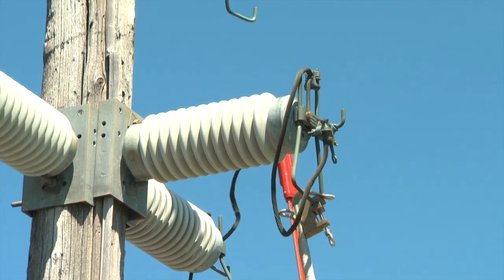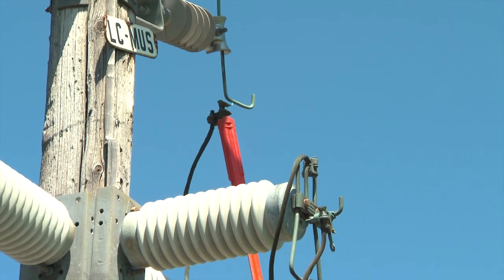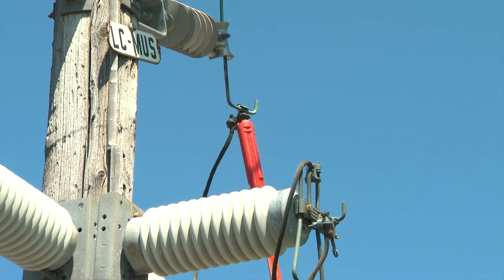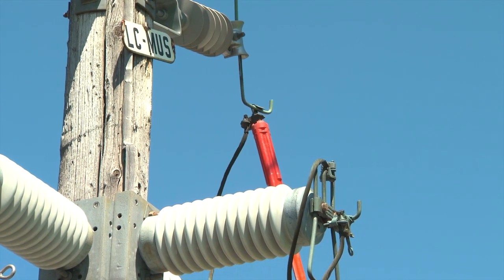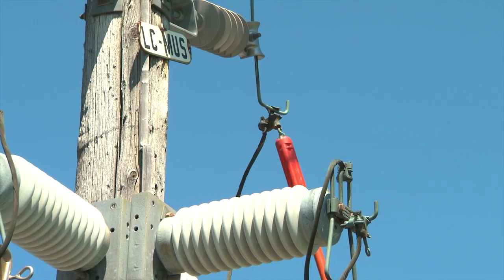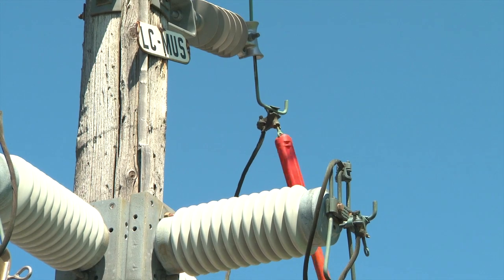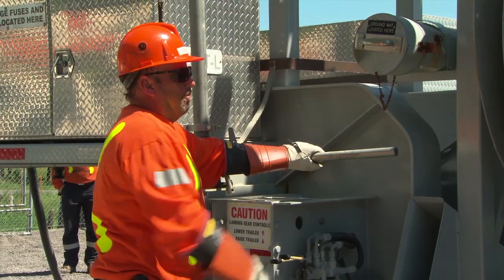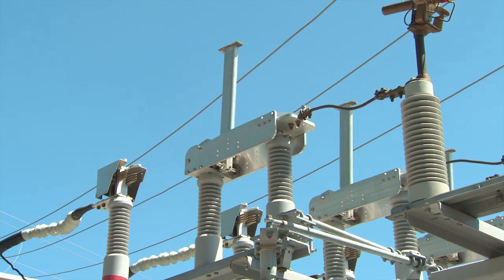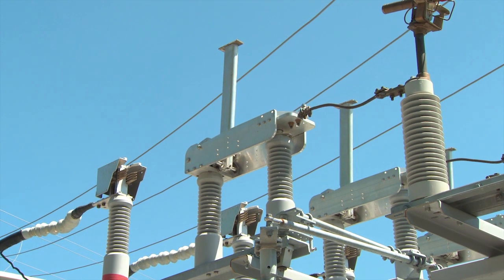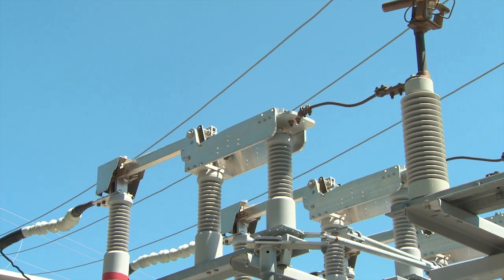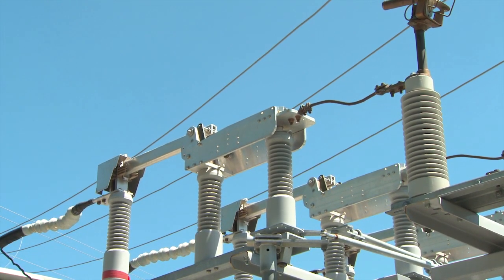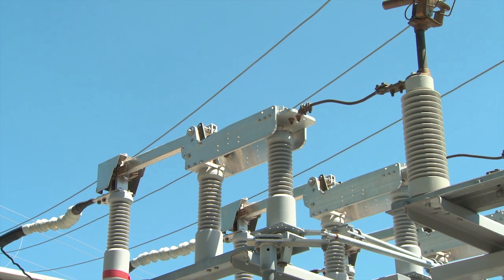This will energize the primary cables to the MUS switch jaw. Be aware of your physical proximity to the cables when performing this task. Close the MUS high voltage disconnect switch. Verify that the switch blades are in the correct position and lock the switch handle. The mobile is now on potential.